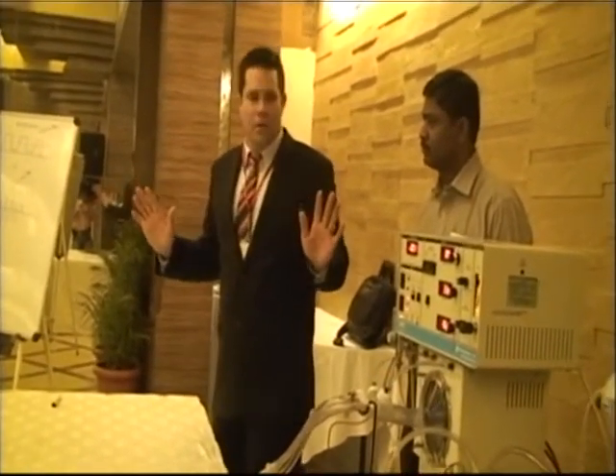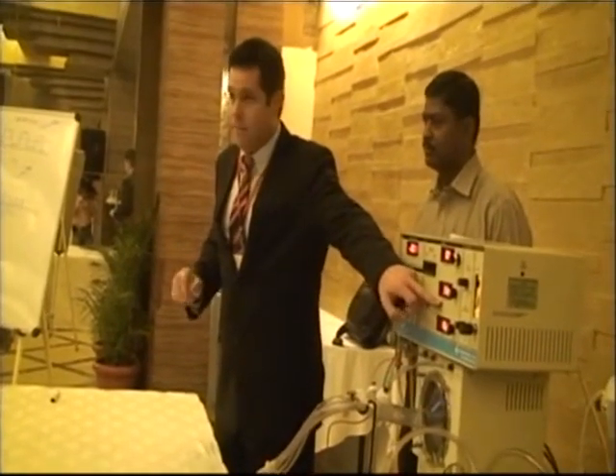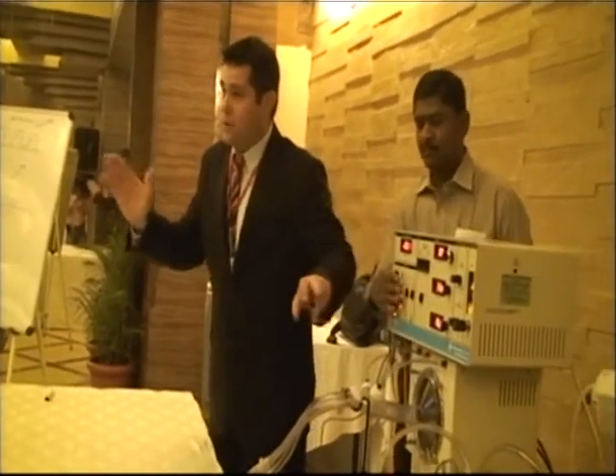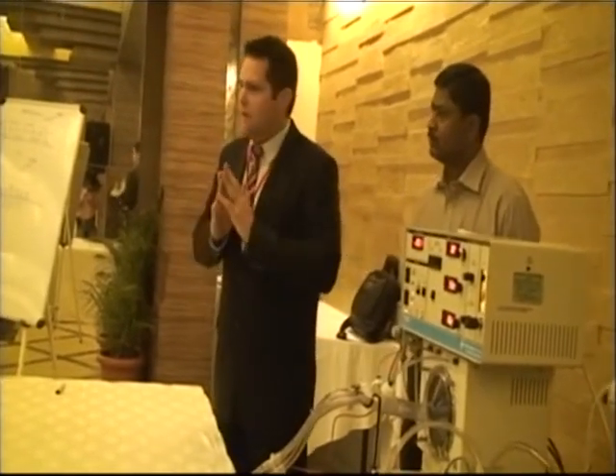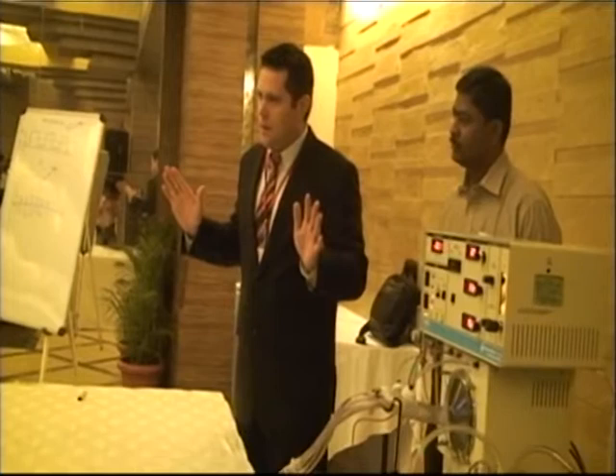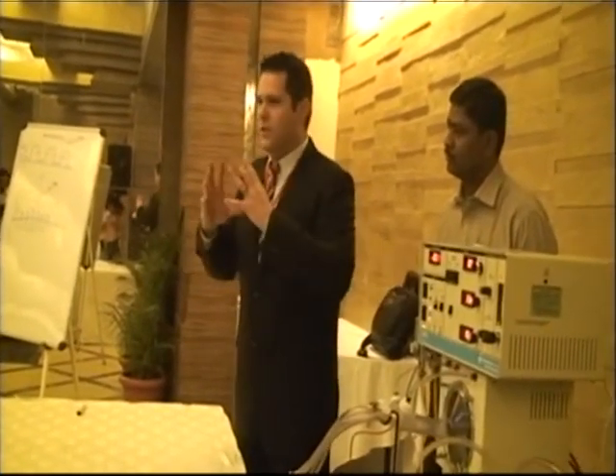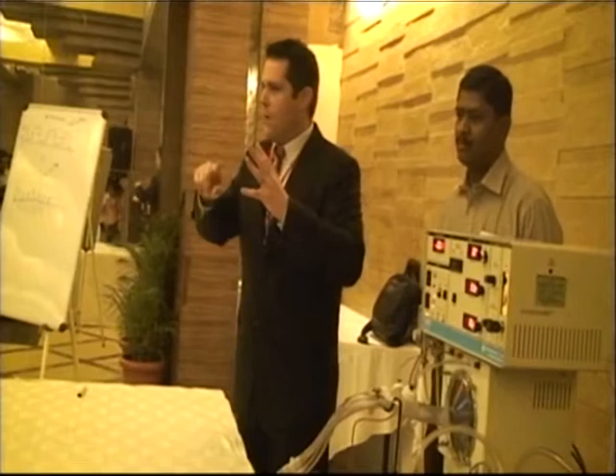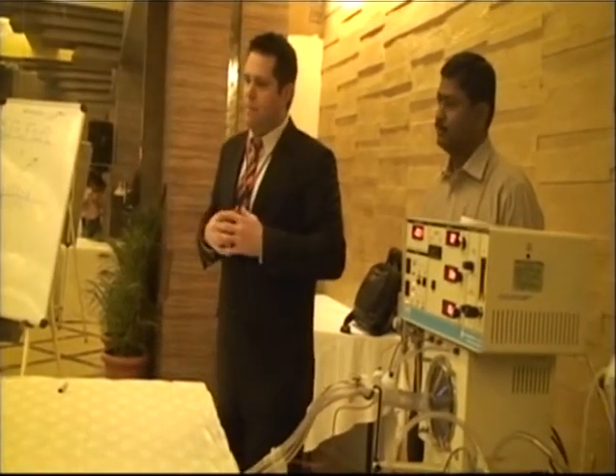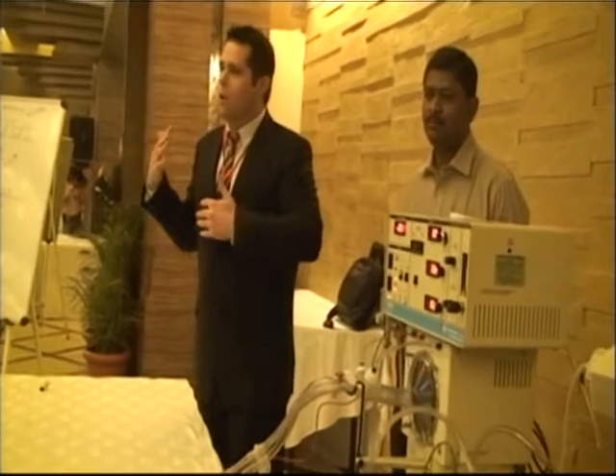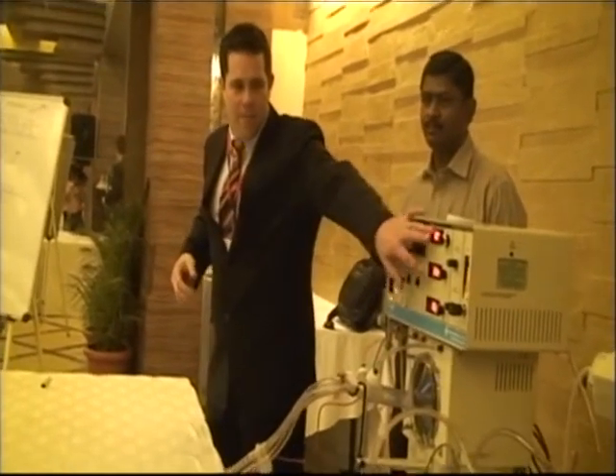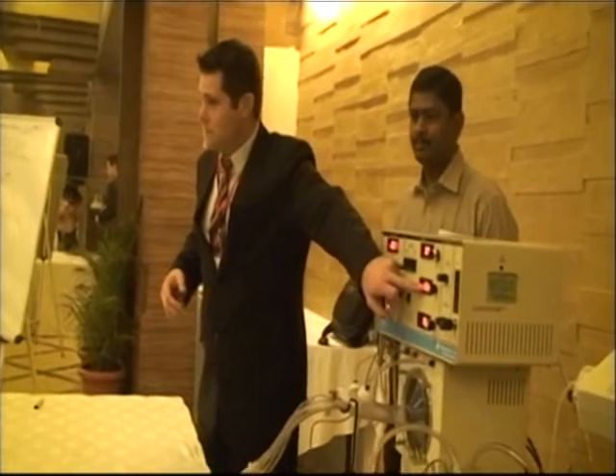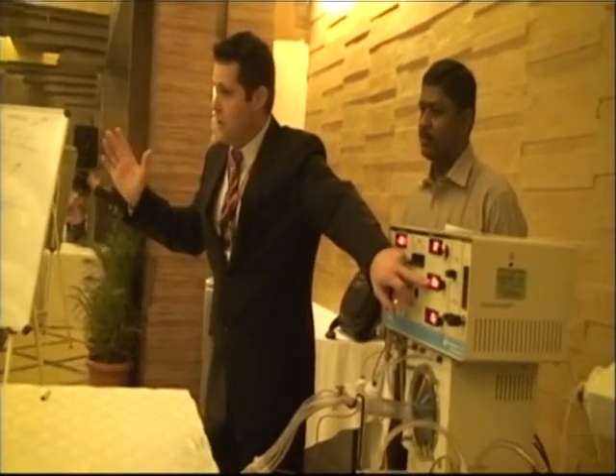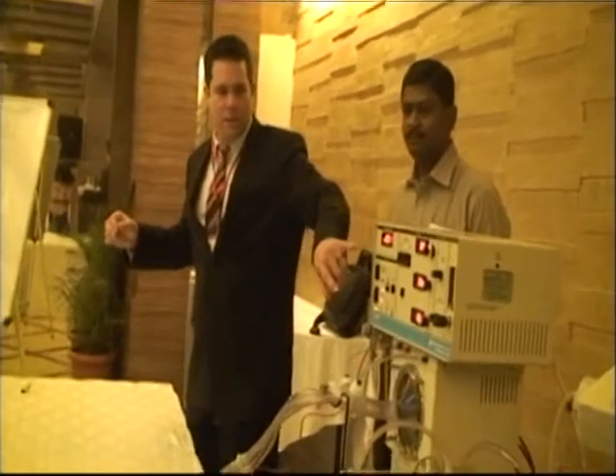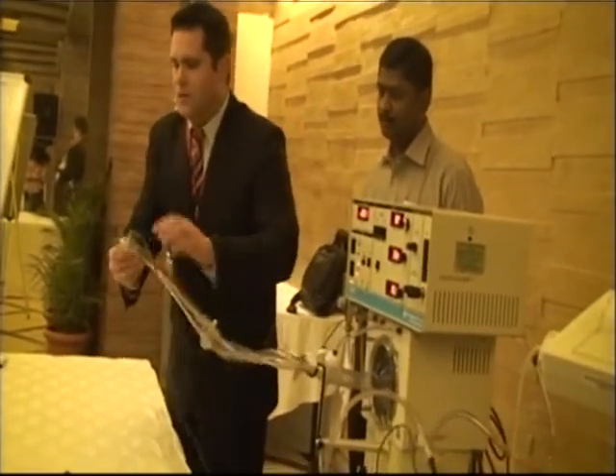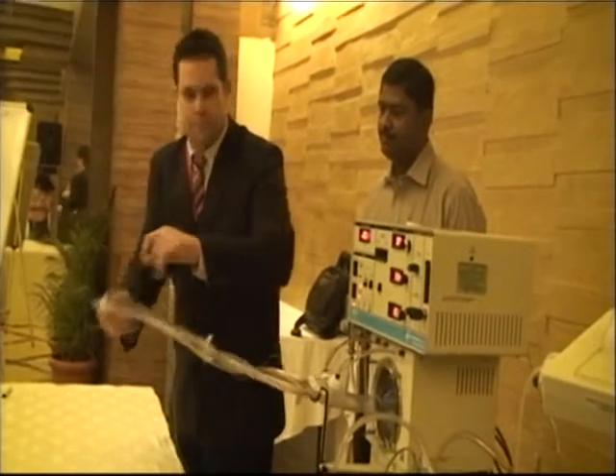In fact, the only time I've ever changed this percent inspiratory time, which helps us determine our I:E ratio, was in a very sick adult that I couldn't manage. By turning this up, we changed the characteristic of the pressure profile being delivered into the lung, and the distal alveolar pressures could more closely approximate what's going on back here. But keep in mind, this should not be set or adjusted. You can do everything you need to do with this at 33%. Also keep in mind that the pressure is being measured downstream here at the patient Y.